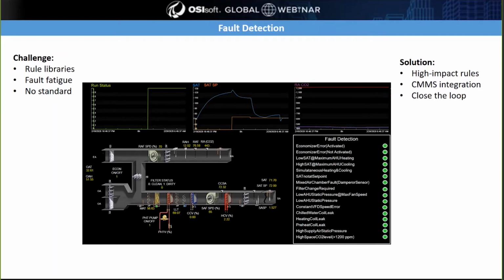And what happens in the space is the terminal boxes or the VAV units that are connected to the air handler, they want more cooling, so they open their dampers. When they open their dampers, the static pressure in the air handling unit will drop, so the fan speed will increase. Eventually what happens is your fan speed is at 100%, the unit's working as hard as it possibly can, but it still can't meet the supply air temperature set point, and that's because it's bringing in 100% outside air. So that's just a way to never meet the needs, always have comfort calls, and spend a lot of money because one single component isn't operating the way it should be.